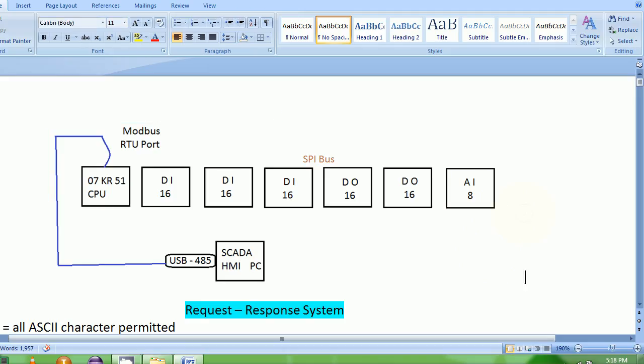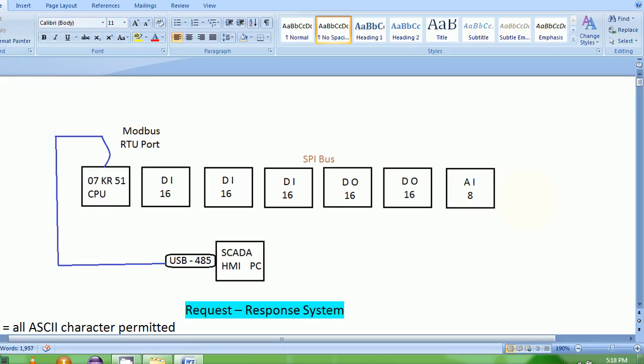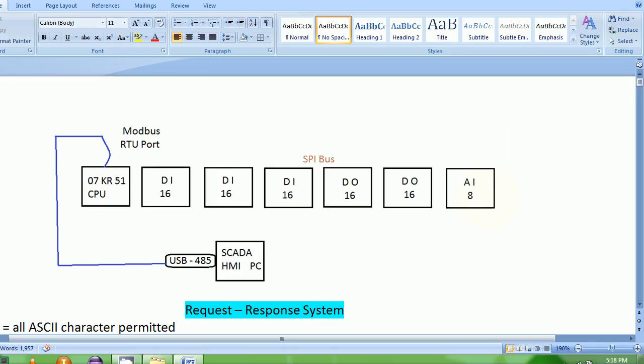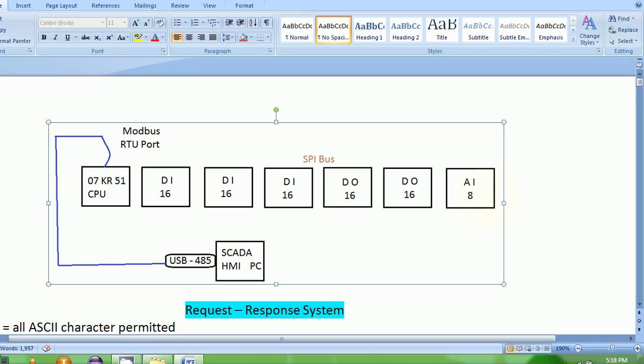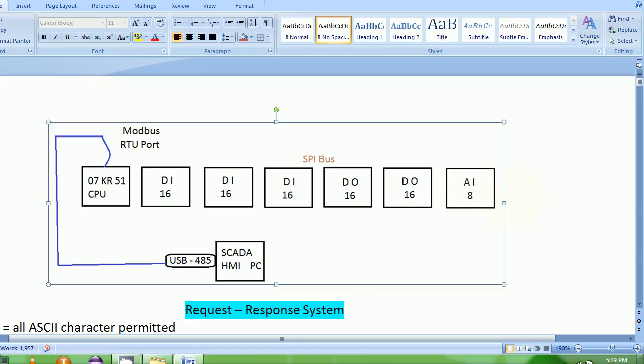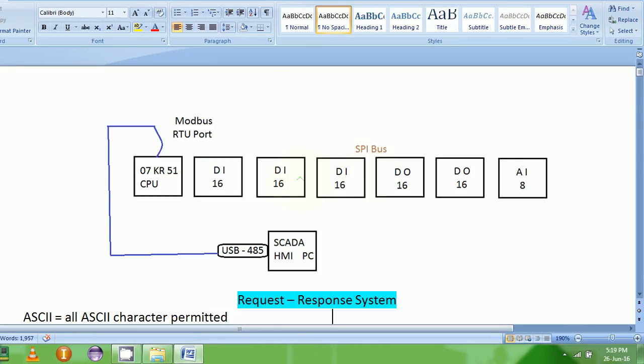Then I've got an analog input module which has 8 channels on it. It's a 4 to 20 analog input. Electronic devices normally count from 0, so I've got my 4 to 20 PT100 input sensor connected to the 7th channel, number 8 if you count from 1. So I've got my PT100 device interfaced on analog input channel number 7. This is how the setup looks.